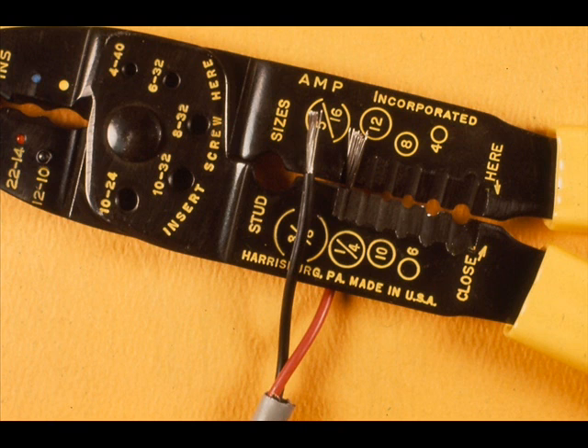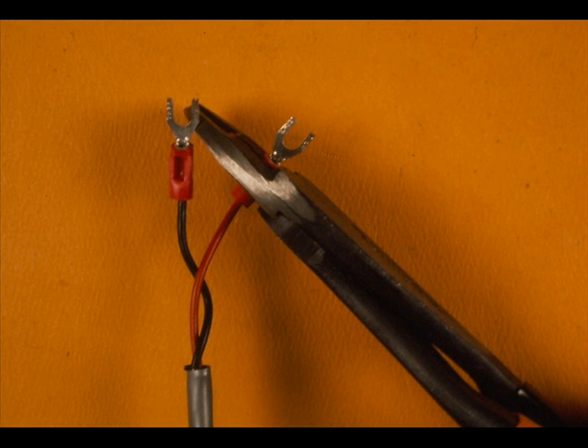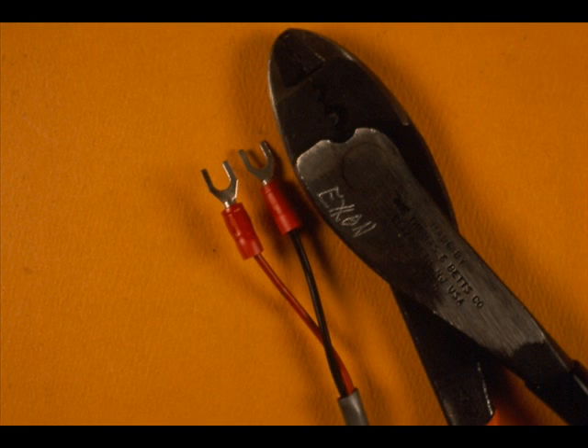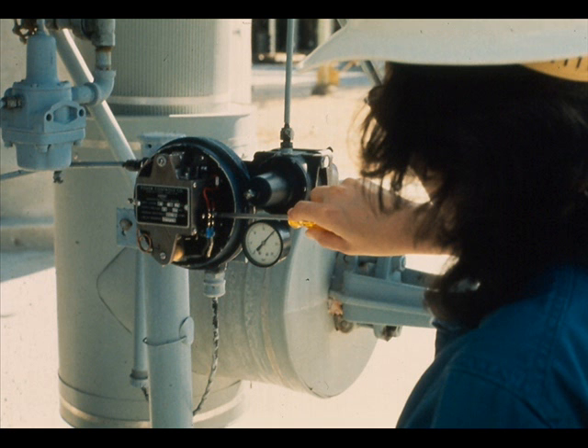Attach the two wire cables to the transmitter and transducer. Remove two inches of cable insulation. Cut off the foil tape and the drain wire. Remove three-eighths of an inch of insulation from the wires. Tape the butt of the cable. Attach wire lugs or terminals to the conductors — be sure you use the correct size crimping tool and wire lugs. Terminate the wires in the transmitter, observing polarity: red is positive, black is negative.